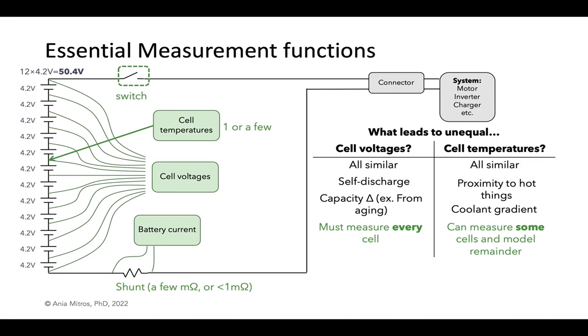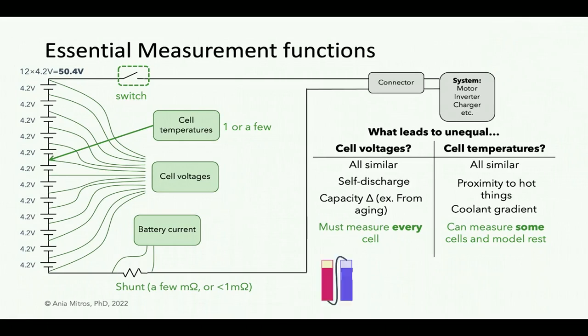Interestingly, though, we must measure every cell voltage, but it's okay to measure only some cell temperatures and model the rest. Can you tell what's different about the processes in the left and right columns of this table to justify this difference? The processes on the left aggregate. If a cell self-discharges more than the rest today, the consequent imbalance will still be in place tomorrow, and tomorrow's self-discharge will increase the imbalance further, and more the day after that.